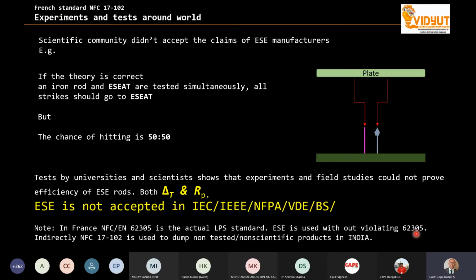Coexist means you have a good guard, which is the 62305 conventional or lightning protection system as per the IEC standard. In addition to that protection, they add one more rod. That's what they mean by coexist - ESE coexisting with the IEC lightning protection system. What they say is: you make a lightning protection as per 62305 standard, and then you add an ESE in addition. Of course, if you have the money, you can do that.